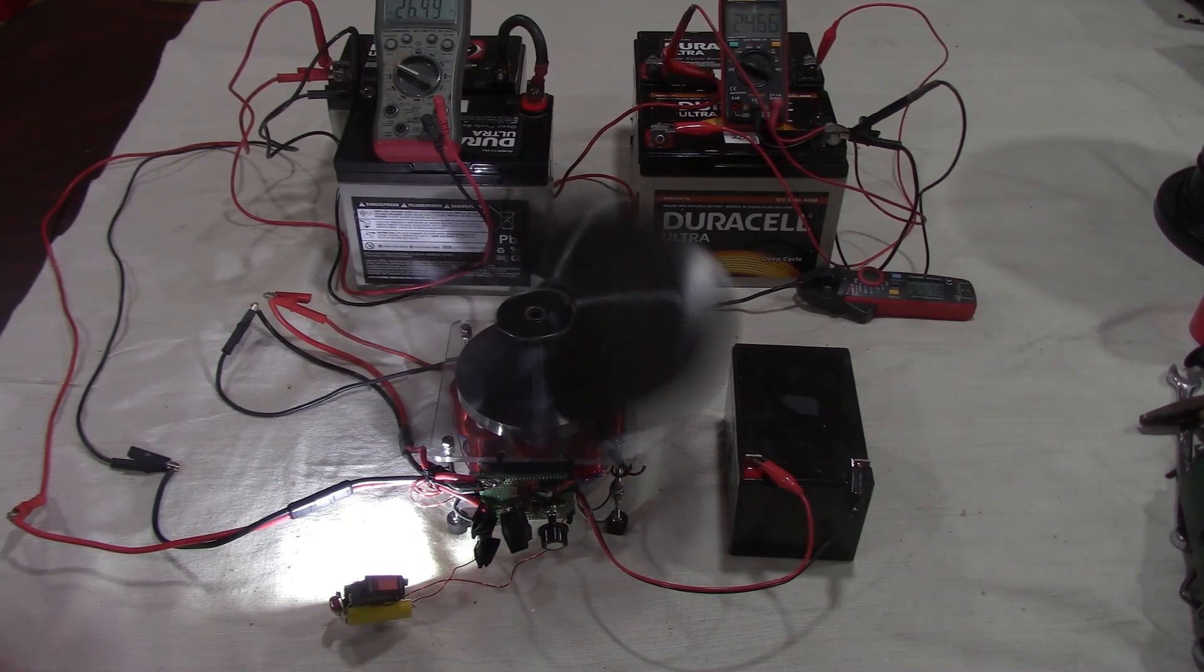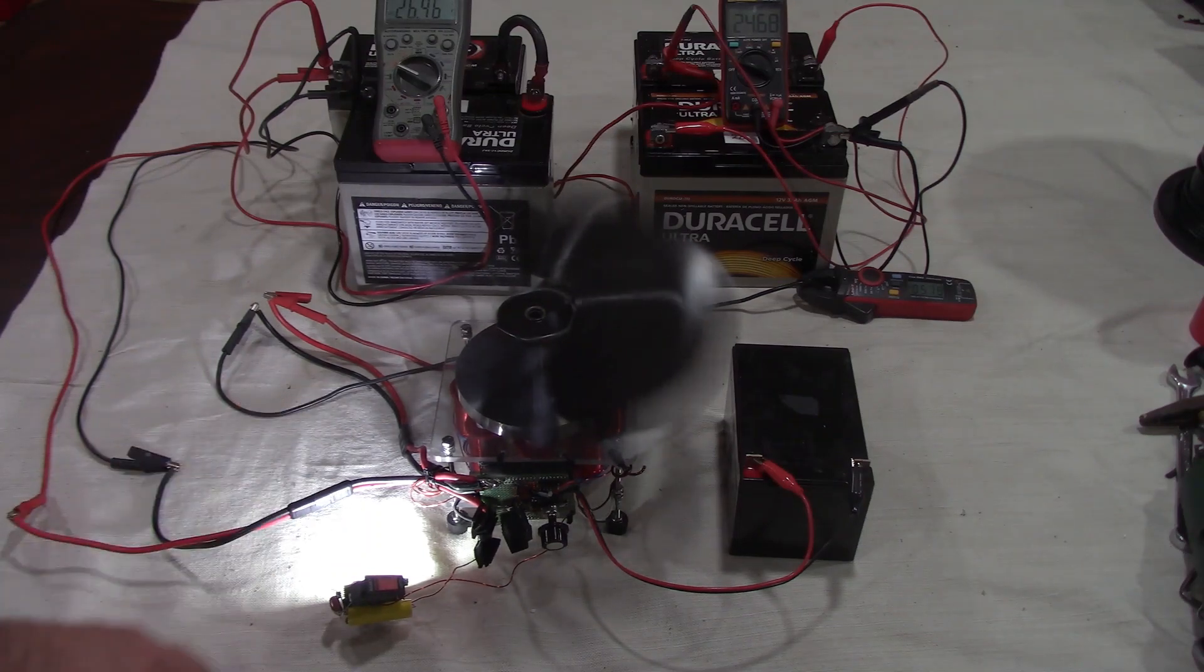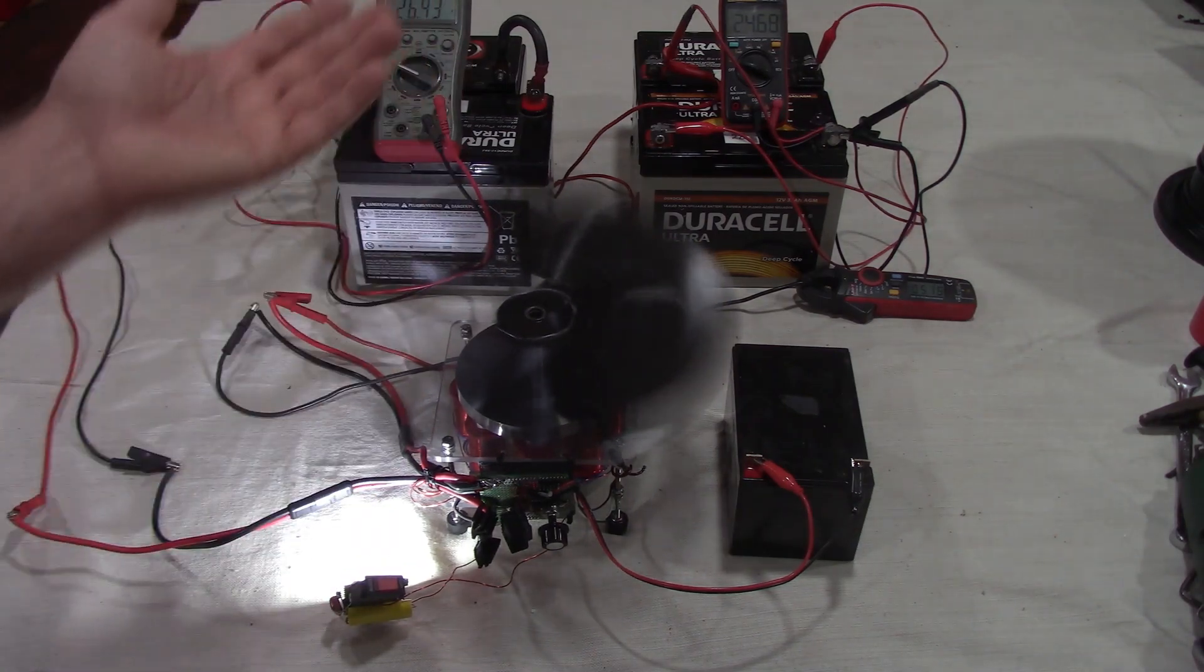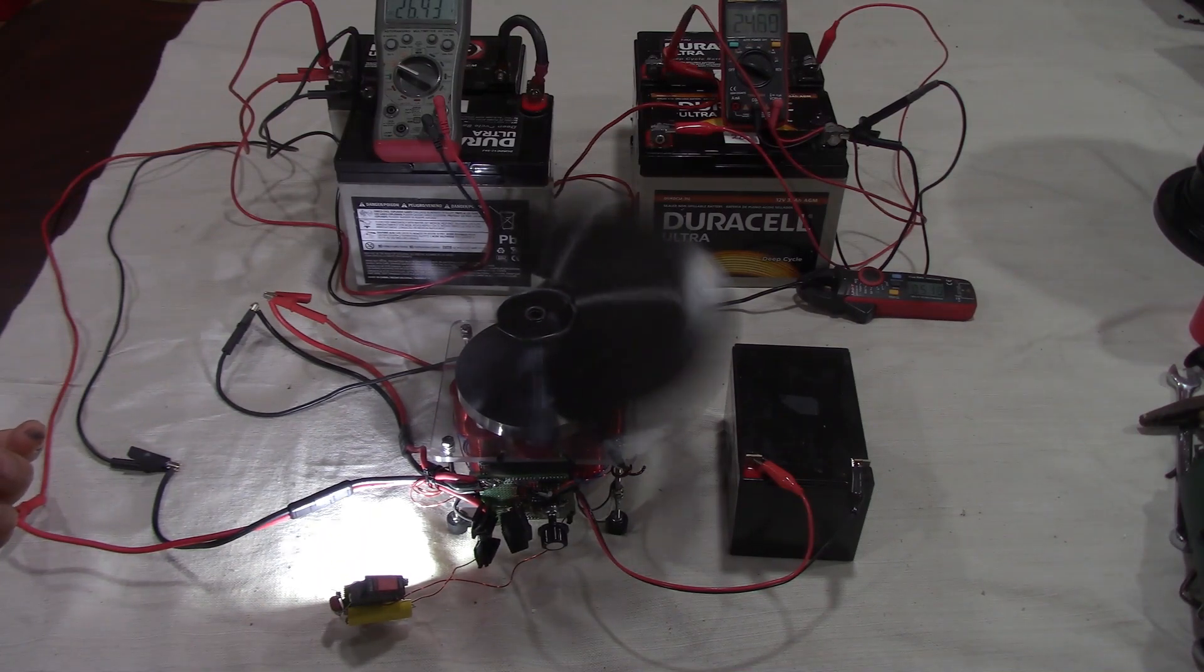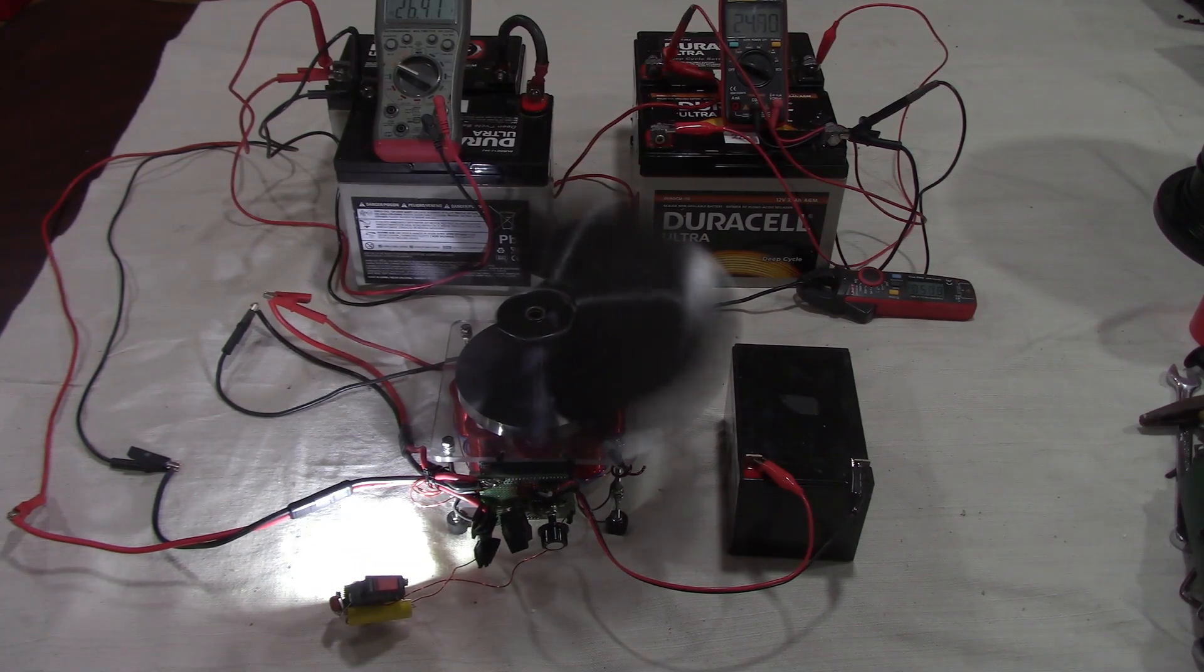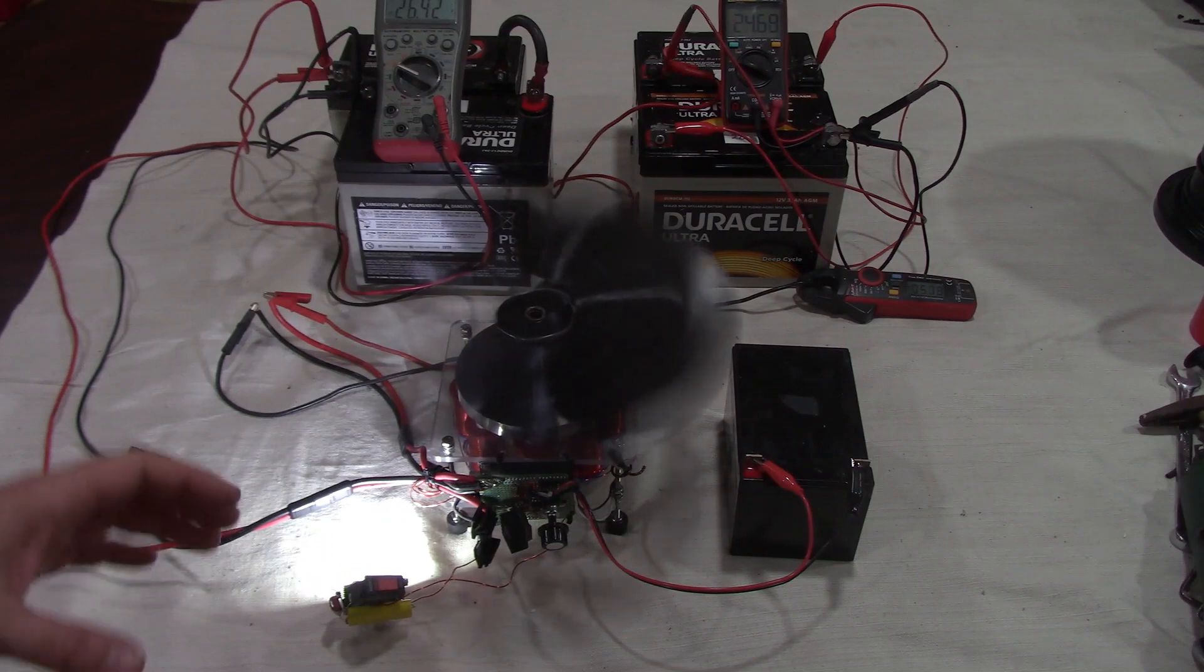I've covered these details before in older videos, but I'll just go over some things. The limitation of the amperage maximum on this motor will be according to the temperature on the coils. The ambient temperature in here is cooler and the air conditioning is on. Of course the fan is blowing, so this is all cooled off. Now the other thing I should mention is, we used to put holes in these plates right near around the bearing so that it can pull the air in from the rotor and distribute it through the coils. We do that in the big motor. But if you want to do that, you can drill some holes there like we did with the EMP motor. You have additional holes for additional coils in there.